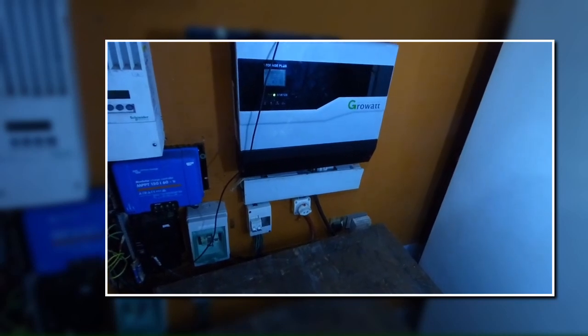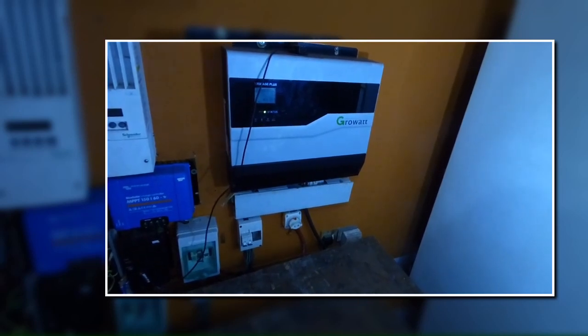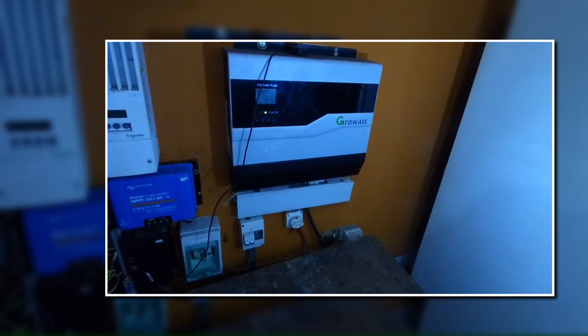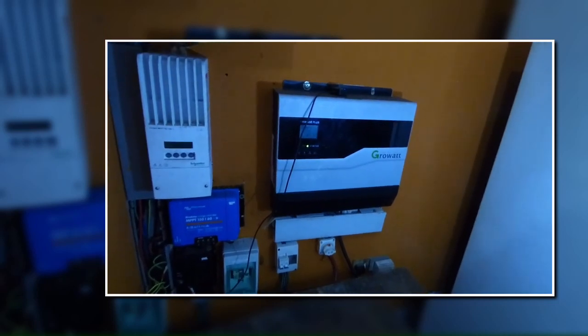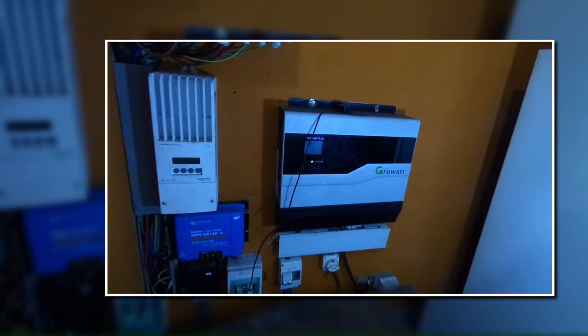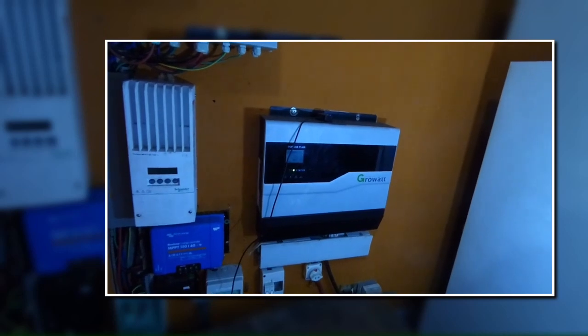Lead-acid batteries don't like being discharged that deep, one, and number two, if you discharge them, they don't like being in a state of partial charge. They have to be fully charged every day. So what am I going to do to mitigate, to prevent this from happening? Well, in Nigeria's rainy season, the bad months were July, August a little bit, but it's been unusually rainy, and it's not just in Nigeria, it's the world over.